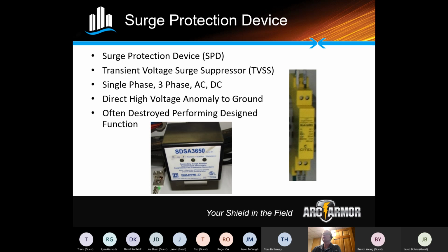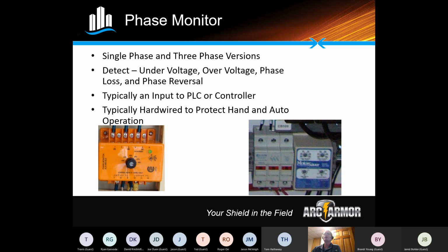All right, moving on. Phase monitors. Typically a phase monitor is designed for single phase or 3-phase. It can detect undervoltage, overvoltage, and phase loss. They're typically input to a PLC or a controller for control, but they're also hardwired into the hand-off-auto switch.